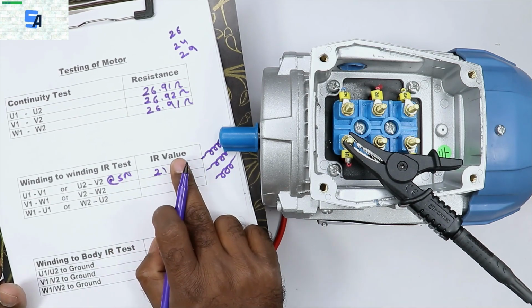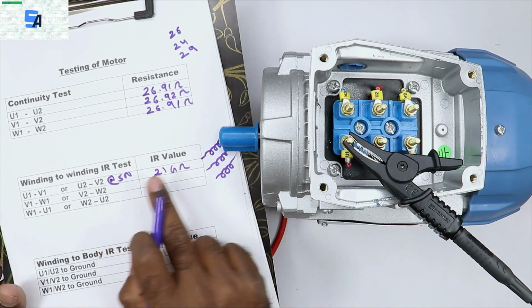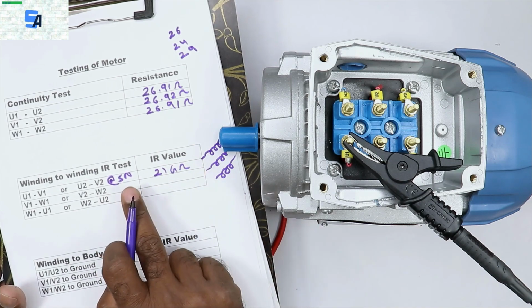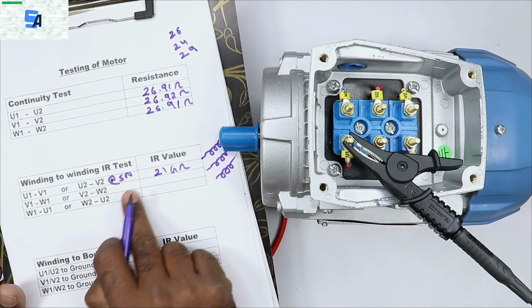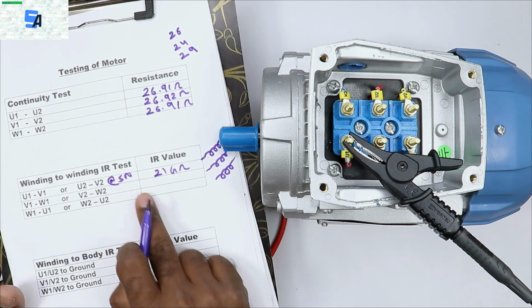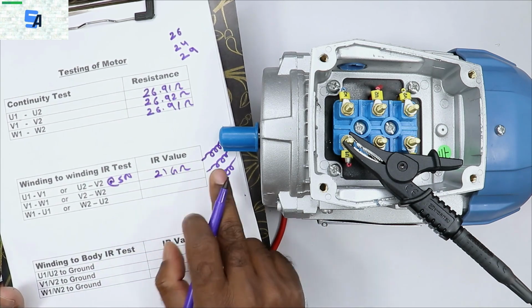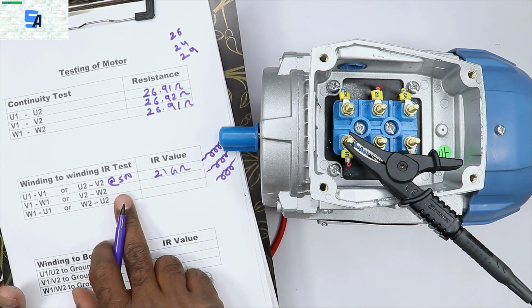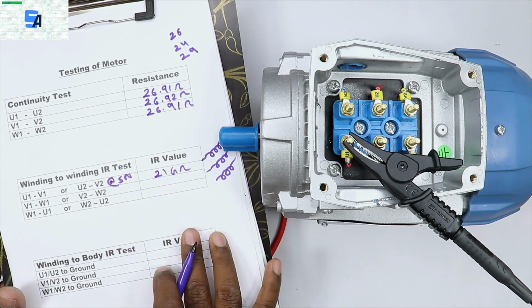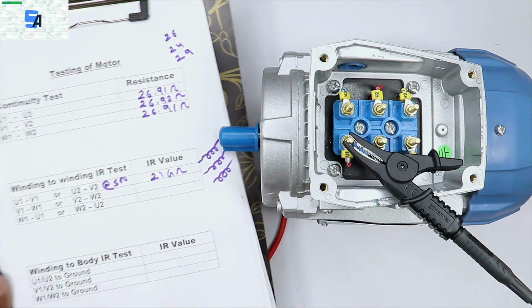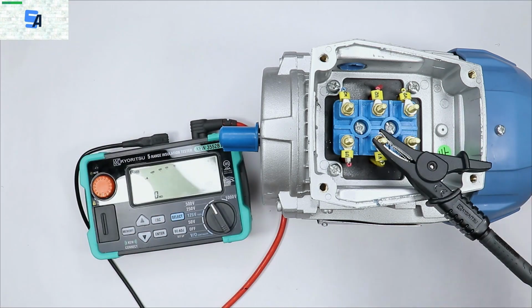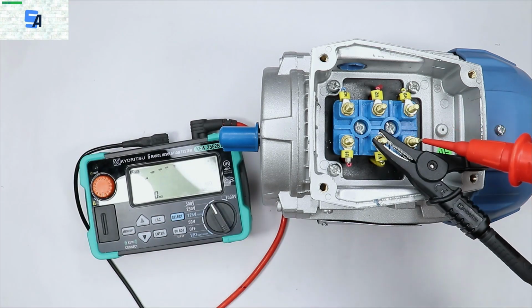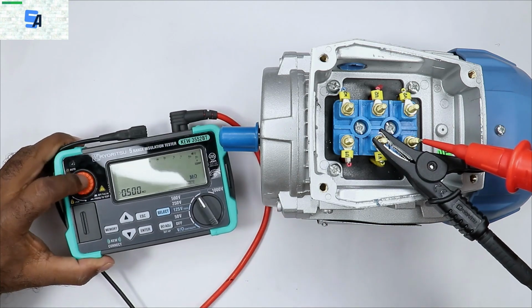Whenever you measure IR value, write down the voltage you are testing at. If you change the voltage, the IR value also changes. So we are using 500 volts here for testing. Now we have to test between V1 and W1. I connected this probe with V1 and the other probe with W1. After connecting, press the test button.